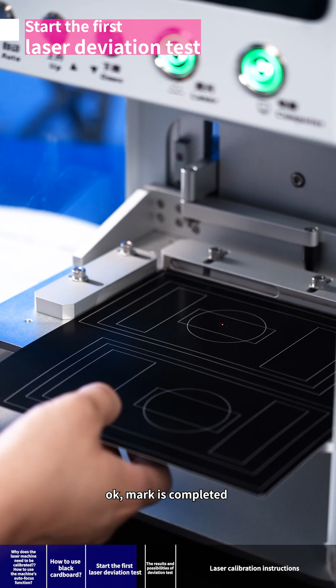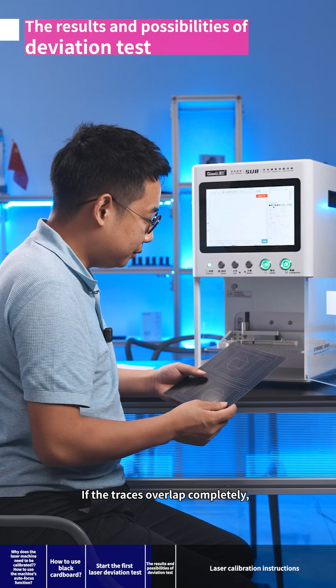If the traces didn't overlap, there are several situations. You can adjust the machine according to the situation you met. If the traces overlap completely, that means the machine is good, normal. It can work directly. When most of the traces overlap well, but some edges and corners do not, this might be because we didn't put it properly. Therefore, we can mark another cardboard again, or in a different direction. Just do cross-validation.